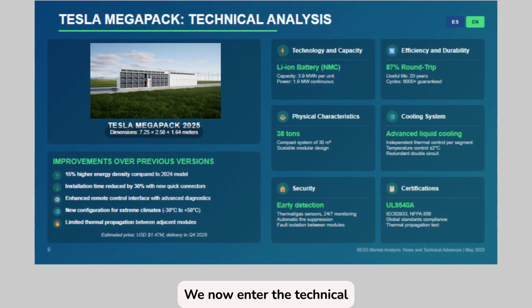We now enter the technical analysis of the Tesla Megapack 2025, one of the most established solutions for large-scale storage. This system uses Li-ion NMC battery technology and offers a capacity of 3.9 MWh per unit, with a continuous power output of 1.9 MW. Its compact dimensions of 7.25 x 2.50 x 1.64 meters and a weight of 38 tons make it a scalable module that can be easily integrated into container-type projects.